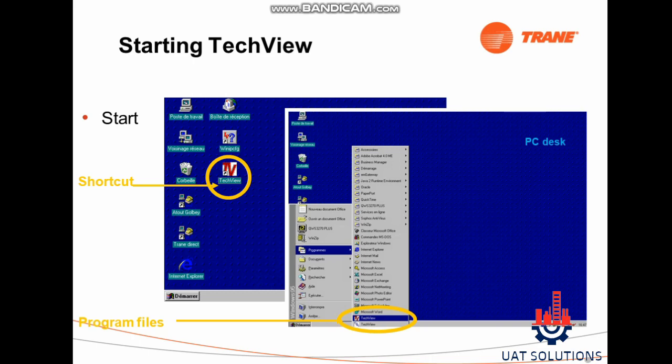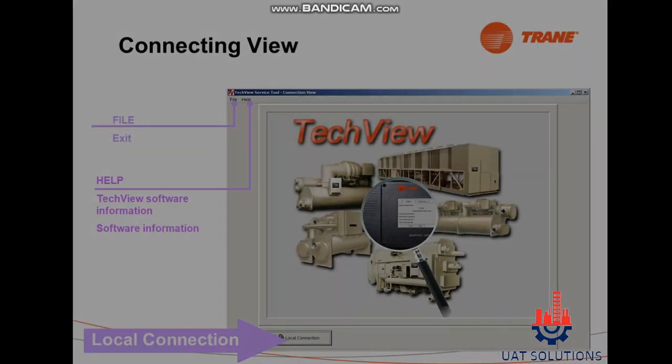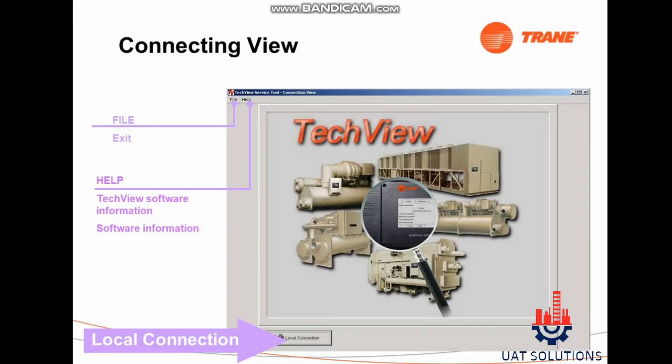We can now move to start TechView. There are two ways to start: one is to run using the shortcut on the desktop, and the second is by going to Program Files. To connect with the chiller, run TechView on the computer and use an RS232 9-pin connector converter, connect the USB side to the laptop and the positive and negative wires on the processor board of the chiller, then click on local connection to start the communication.